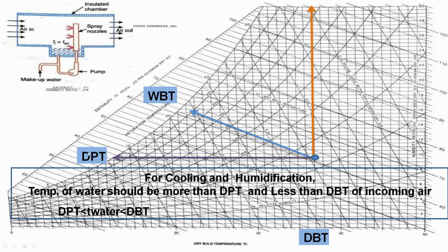One important condition for the cooling and humidification process: the temperature of water should be greater than the dew point temperature (DPT) of the incoming air and less than the dry bulb temperature (DBT) of the incoming air. So DPT < T_water < DBT.